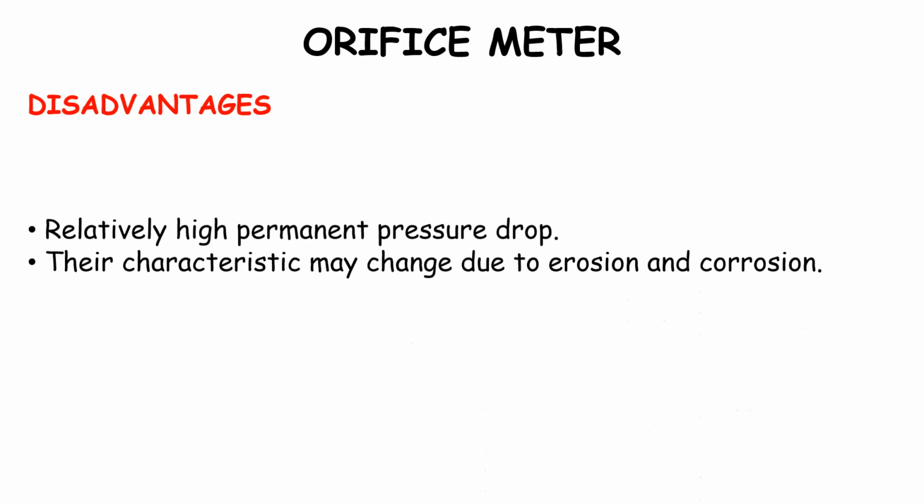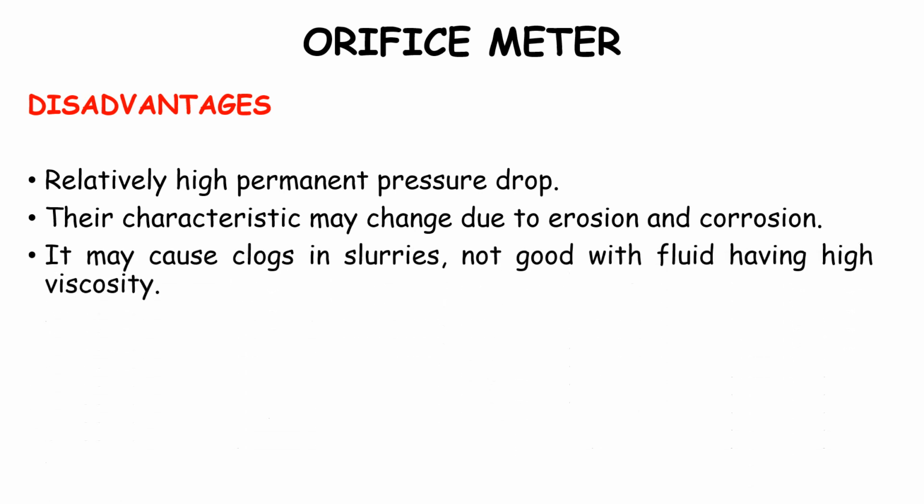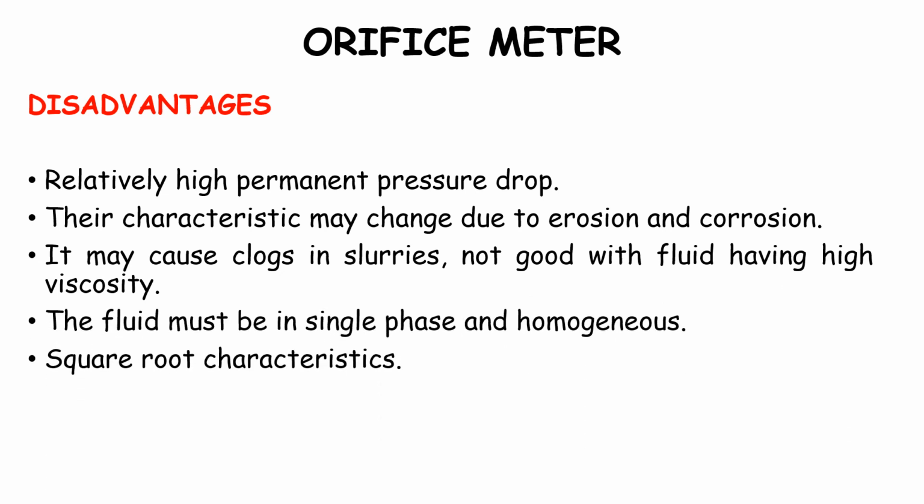The disadvantages are a relatively high permanent pressure drop. The characteristic may change due to erosion and corrosion. It may cause clogs in slurries, not good with fluids having high viscosity. The fluid must be single phase and homogeneous, and it has square root characteristics. With this we have come to the end of the orifice meter.